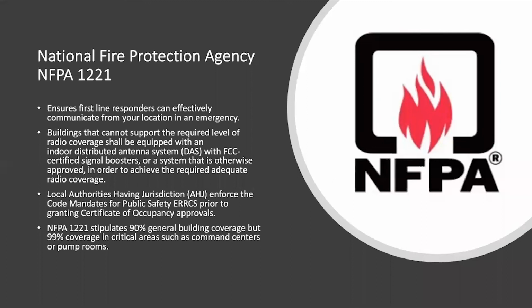NFPA 1221 has a more comprehensive role for the AHJ, which is the local government entity that oversees these systems. I won't read through all the text on this slide, but it's a comparison of key code requirements that have evolved and are for the most part aligned between the IFC and NFPA codes and standards. The requirements listed here are pathway survivability, which is the requirement for cables to be protected from fire damage to a specific heat level for a certain amount of time.